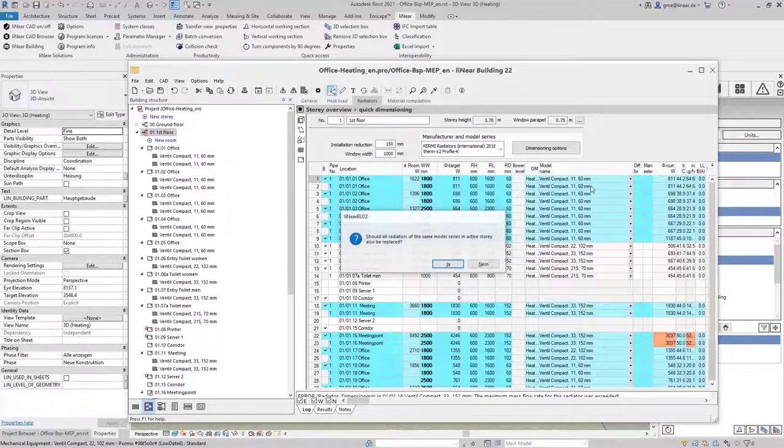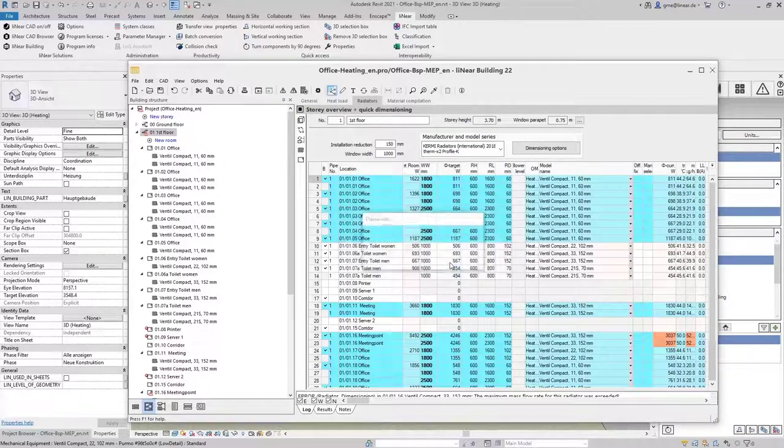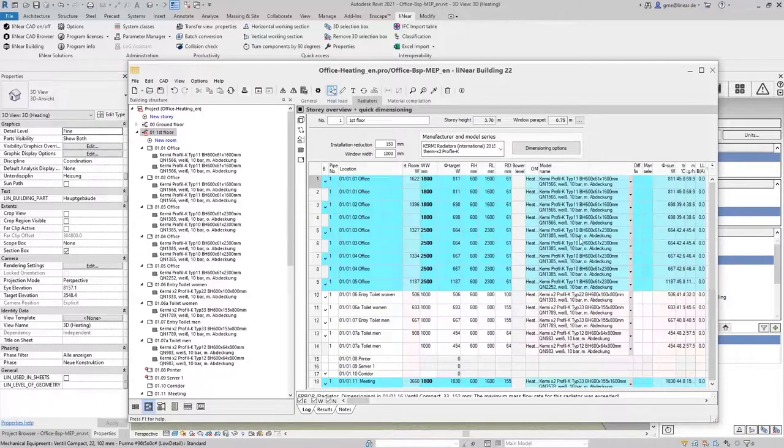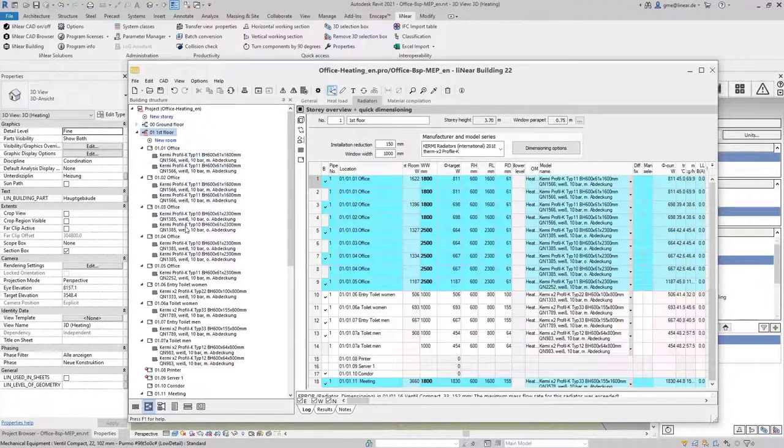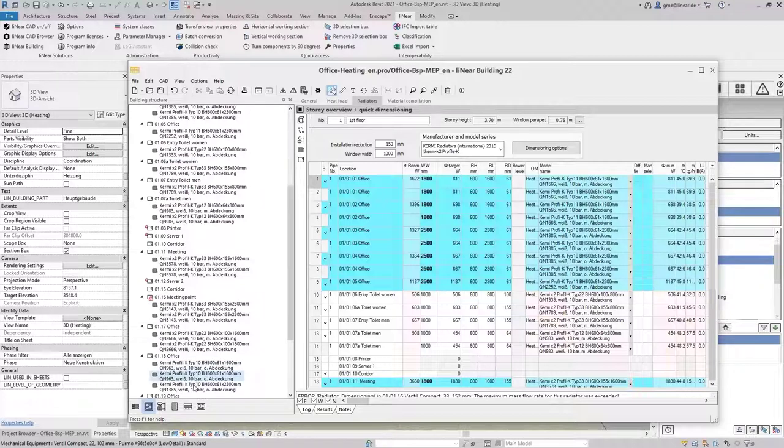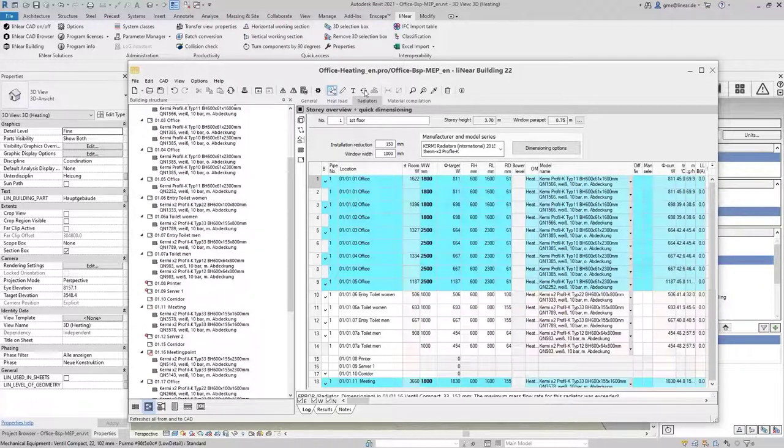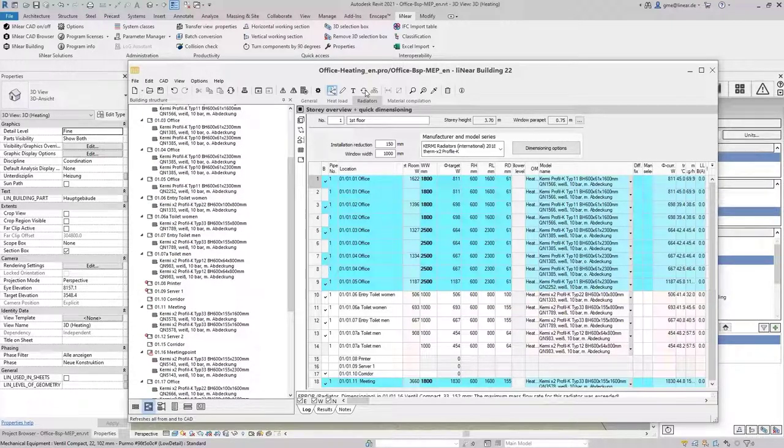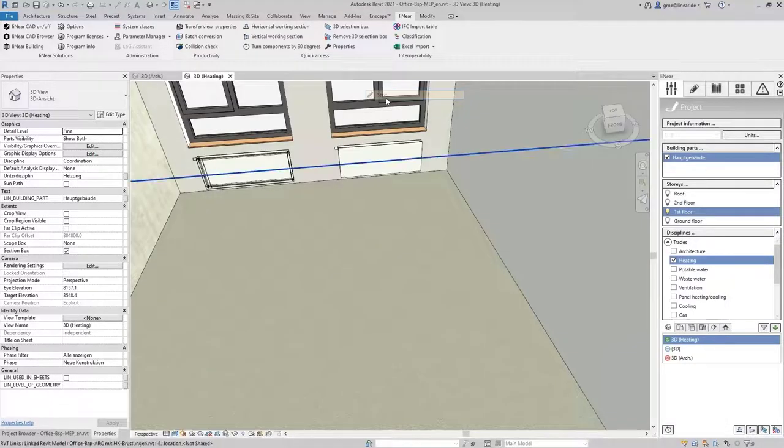If I change the radiator type the program asks me if I want to exchange all radiators of this kind. I agree and now the radiator dimensioning is carried out again with a new radiator type and also in this case I use the refresh function again and thus transfer our changes to the model.